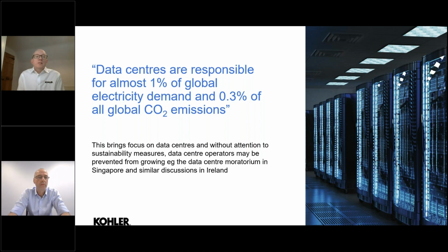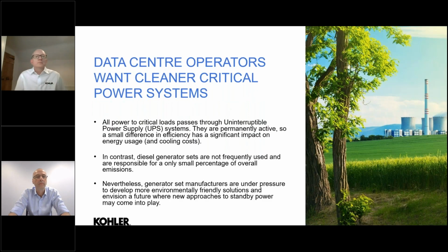So developing new data centres, we've seen moratoriums in places such as Singapore, and of course there's similar discussions going on in Ireland. So data centre operators want cleaner critical power systems. Today, all power to critical loads passes through a UPS. They are permanently active, so a small difference in the efficiency has a significant impact on the energy usage and, of course, the cooling costs.